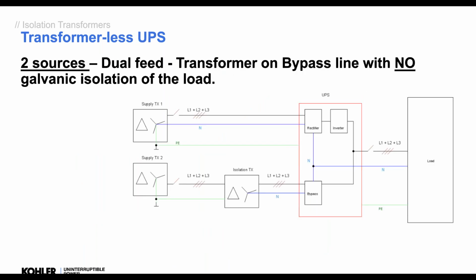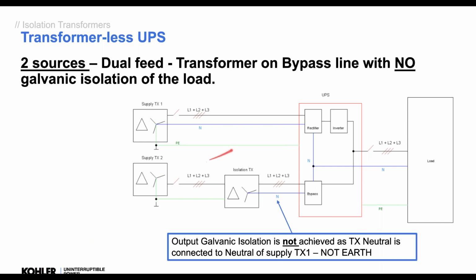Okay, nowadays our UPSs have a four-wire connection on the rectifier and a four-wire connection on a bypass. So we need to put a transformer in place so we don't connect the neutrals together from the PES. Okay, so we're having this, and this is in reference to this neutral. Okay, so we don't have an issue. It is not a galvanic isolation. We're not re-earthing it at this point. Okay, and that is the big difference. We're isolating the two supplies.